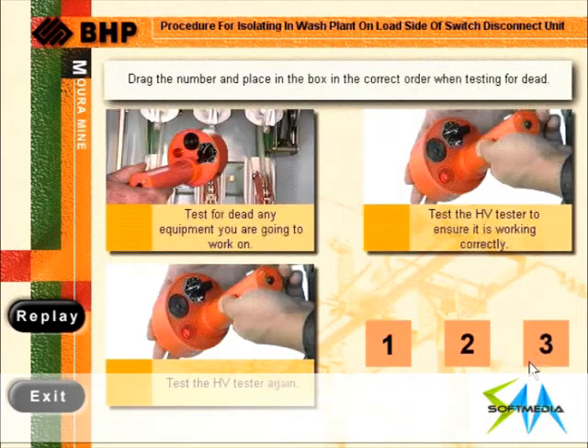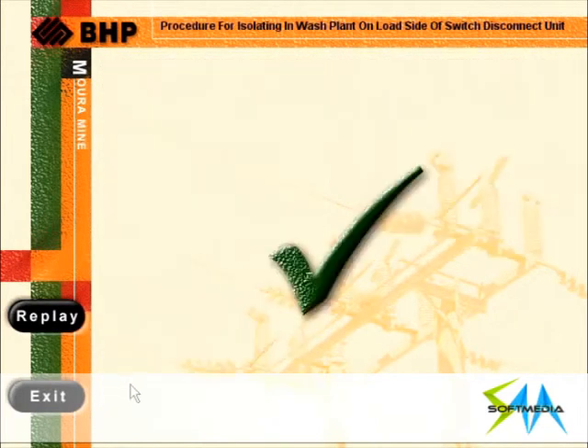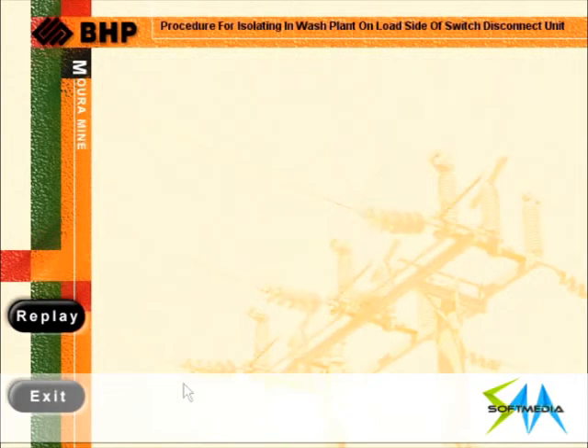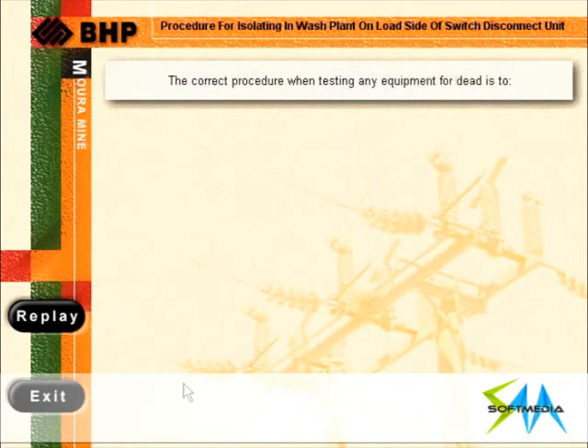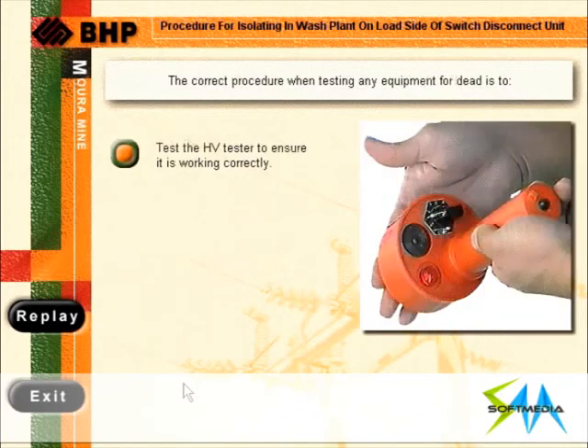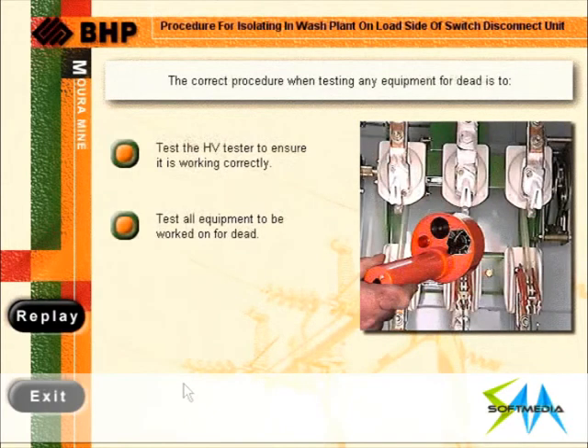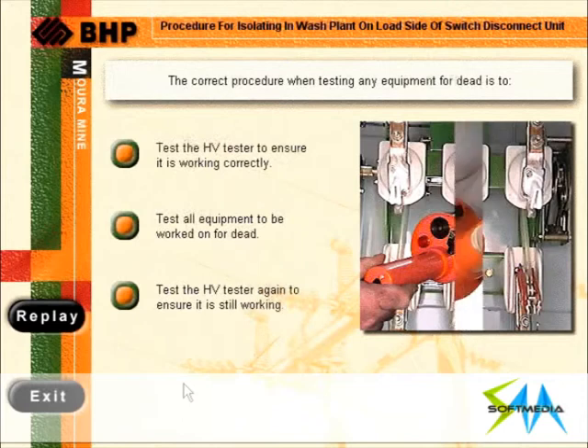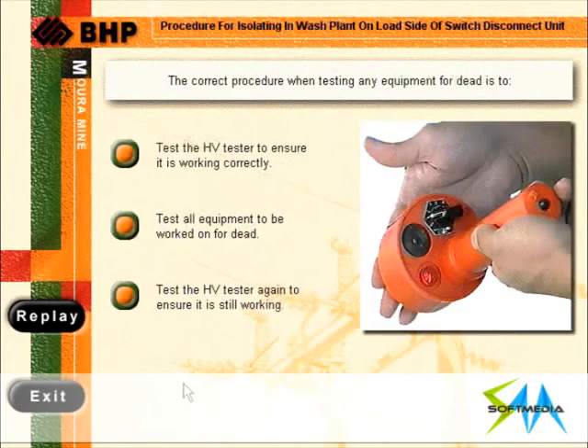Drag a number and place in the box to show the correct order when testing for dead. Yes, that's right. The correct procedure when testing any equipment for dead is to test the high voltage tester to ensure it is working correctly. Test all equipment to be worked on for dead. Test the high voltage tester again to ensure it is still working.